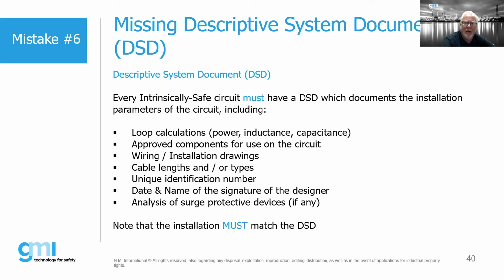We want to see our loop calculations, whatever components are used on that circuit, our wiring installation, the cable lengths and/or types, any unique identification numbers, date and name of the signature of the designer, and if we're using any surge protective devices, we should have that as well. And again, we need to have a DSD to compare that to what actually gets installed in the field. This is, again, one of the biggest issues that, as an inspector, I don't find this. And it's really the responsibility of the designer or the OEM to be putting this information together.